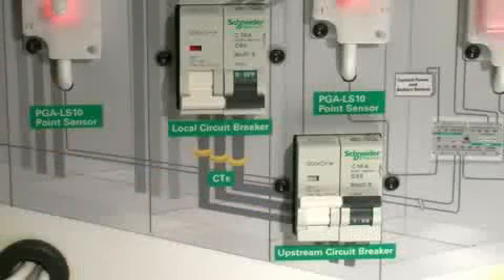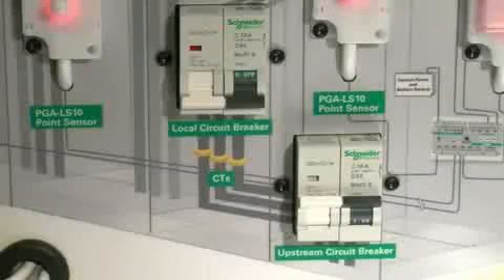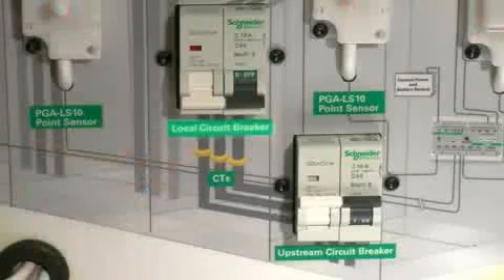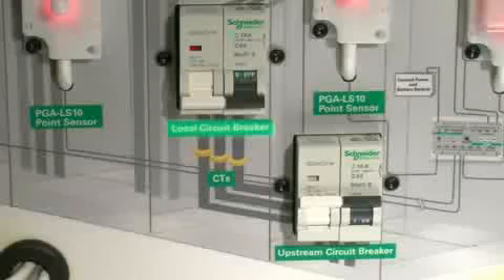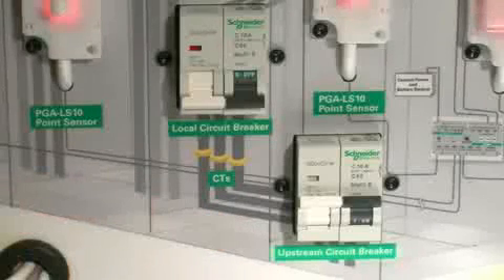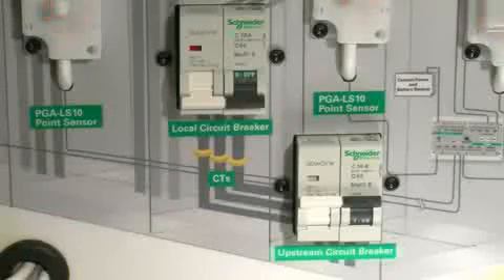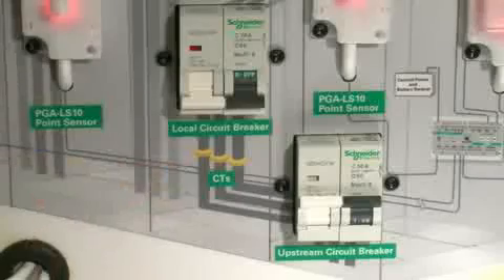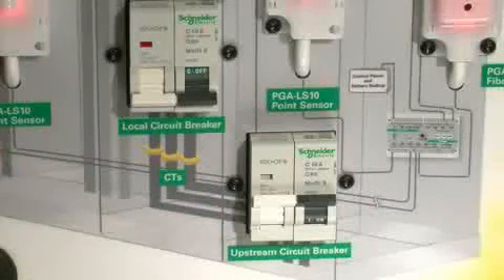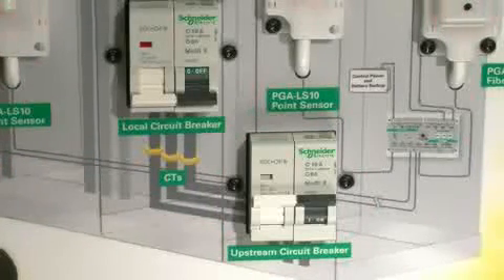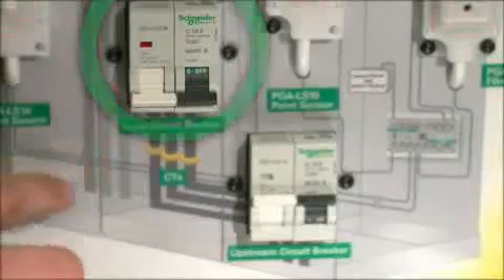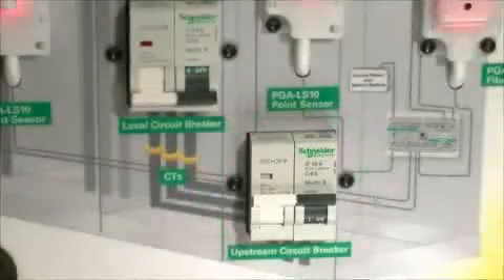These two breakers represent breakers that would be upstream of an arc fault. Breaker 1 is going to be the breaker that's directly above the fault. Breaker 2 is going to be the distribution breaker that's actually above the breaker that was feeding our subset. This breaker reacted, this one did not, because we're tied into this one. We do have another feature in our relay where if this breaker were to jam, we could then trip this breaker off that actually feeds that main breaker.